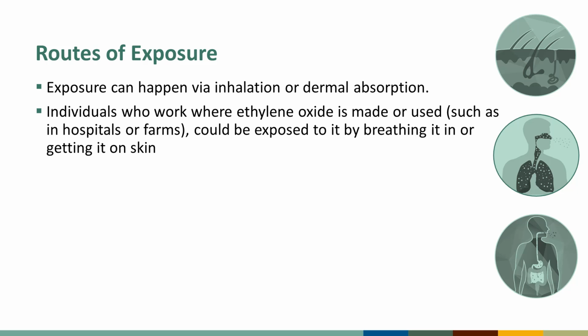Examples of situations in which workers may be exposed include the following: during changing of pressurized ethylene oxide gas cylinders, from leaking valves, fittings, piping, and sterilizer door gaskets, when opening the sterilizer door at the end of a cycle, from improper ventilation at the sterilizer door, from an improperly ventilated or unventilated air gap between the discharge line and the sewer drain, during removal of items from the sterilizer and transfer of the sterilized load to an aerator, from improper ventilation of aerators in aeration areas, from incomplete aeration of items, from inadequate general room ventilation, and when passing near sterilizers and aerators during operation.